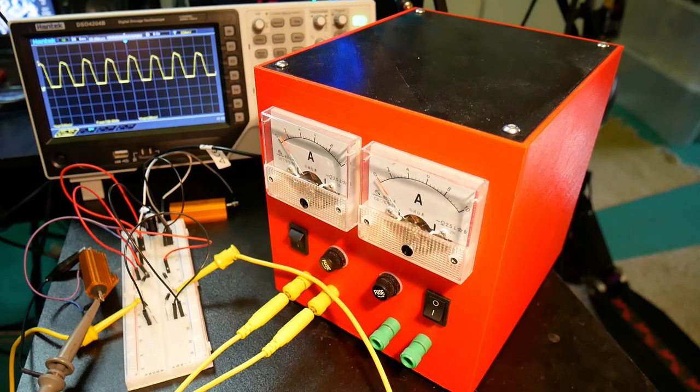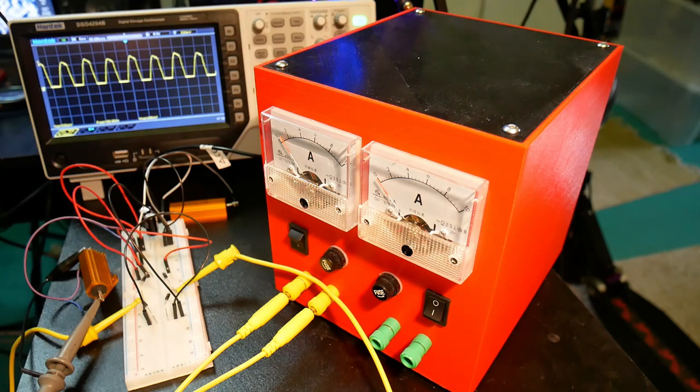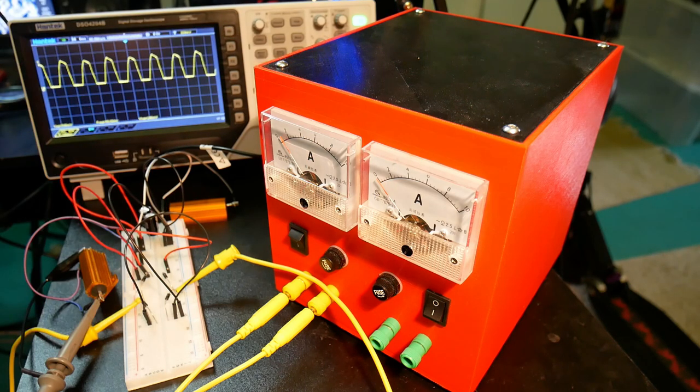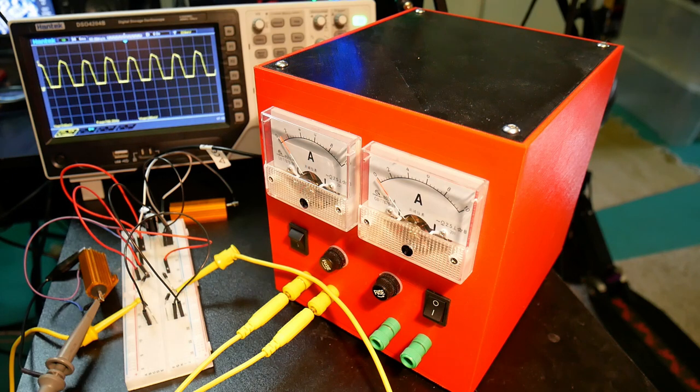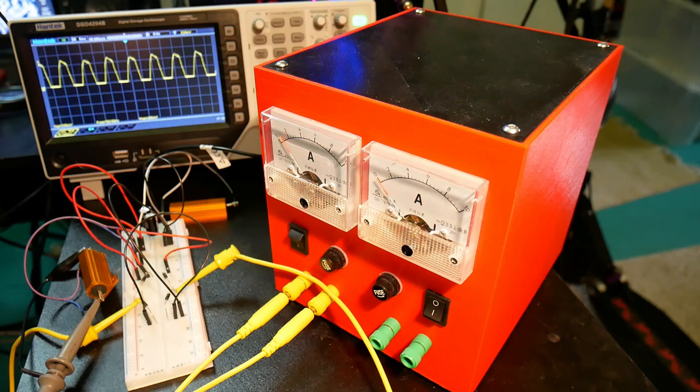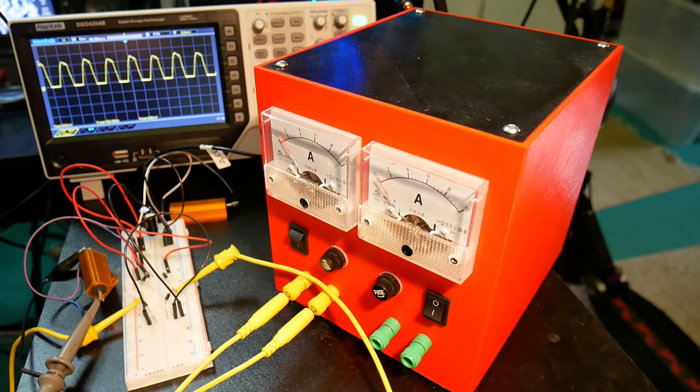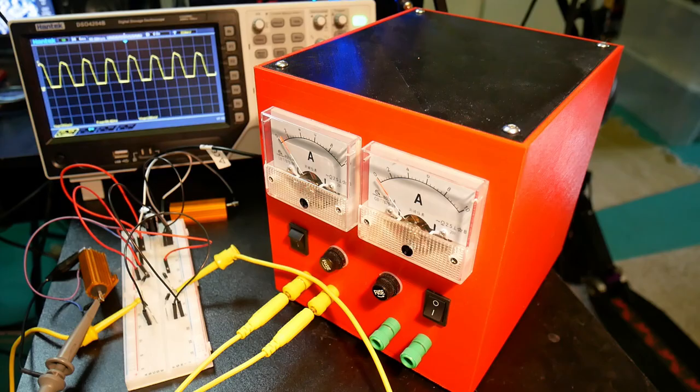And then if it isn't taken into account, then you might actually overheat the transformer. You know, just trying to reduce the ripple using lots of very big capacitors, and you end up with this problem. And it's a hidden problem. If you're not measuring the current, you won't notice. You'll just look at the ripple and say, oh, everything's okay.